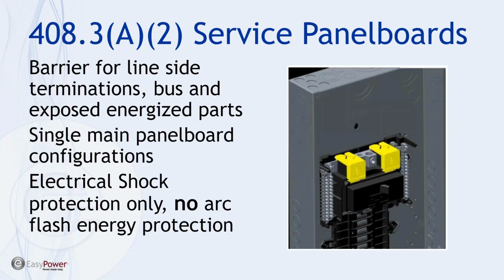Now, for new construction, panels are required, according to Article 408.3, to have a barrier on the line side termination to prevent accidental contact. And so the question is, does this help with arc flash? Well, the most common initiating event causing arc flash is incidental contact, often while removing panel covers. But the guideline to exclude the main breaker in a panel is really a function of the potential size of the plasma ball. I've had people respond that, well, we don't really need to worry about this main breaker isolation thing now that we have this barrier. And again, I think this shows a little bit of a misunderstanding of what's going on in arc flash calculations.